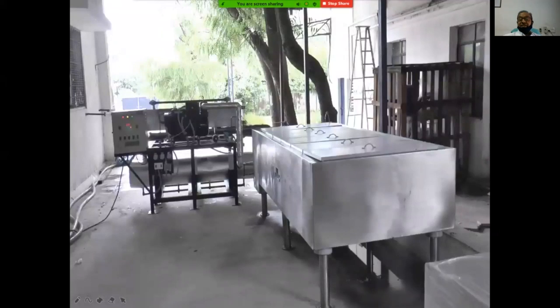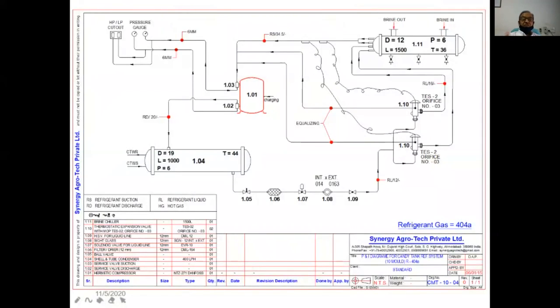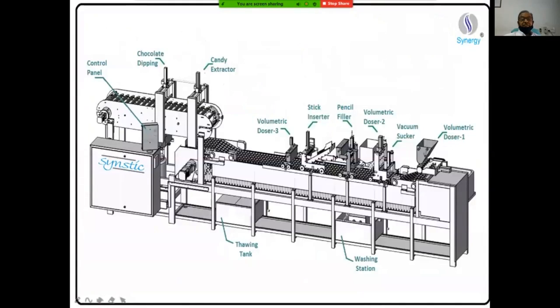This is the brine system, where I explained to you brine cooling is to be done. The refrigeration system for the brine cooling is a simple, single stage system. Only here we put two expansion valves because there are two inlets in the chiller. This is the automatic stick line, where brine has been circulated, and this conveyor is moving and extracting and making the chocobar or any product. How it looks, you can see.